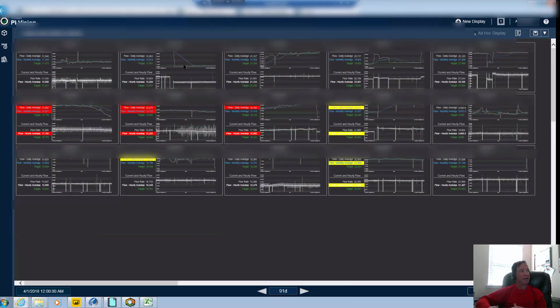How about every day I get a report or an email notification that says, here are the pieces of equipment that are out of spec today. If I start to see a long-term trend, then maybe I go look at the trend. I keep seeing the same piece of equipment show up. Or maybe we even write some analytics that say, if a piece of equipment shows up on the report and is red for a week consecutively, we drop you an email and say, you probably ought to go look at this. Let's say you don't have time to look at this particular display every day. That way you have proactive knowledge that there could be a potential equipment problem, and now I can take proactive care of it.